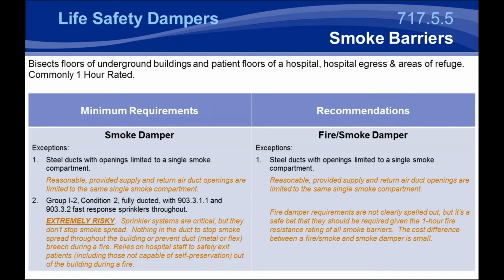Now, smoke barriers are commonly 1 hour rated, but can be 0 hour rated as they're not a fire barrier. And basically, they bisect floors of underground buildings, but more commonly bisect patient floors of hospitals or other areas of refuge. Now, there was a change to the code in the 2015 code cycle where the fire protection group for hospitals lobbied to remove smoke dampers in smoke barriers in Group I-2 buildings that are Condition 2, that have fully ducted systems that are sprinklered with either regular or fast response sprinklers.